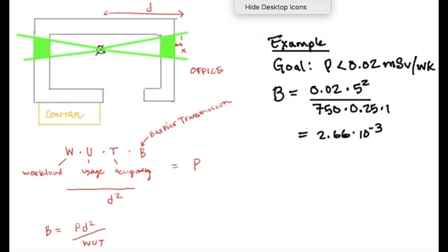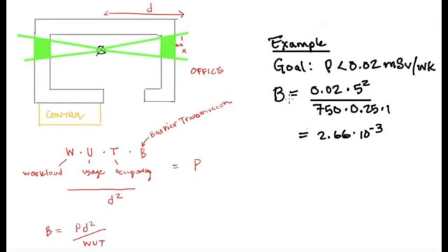All right, so you will say, oh, well and good, Dr. Ford, but how thick of concrete do I have to pour to shield this LINAC? So let's do that. Let's calculate the thickness. We're almost there. So thickness we're going to express in terms of the number of tenth value layers, number of TVLs.